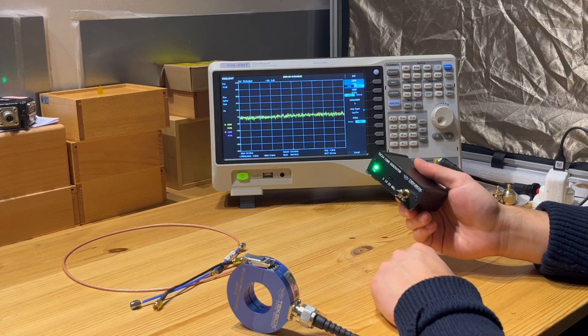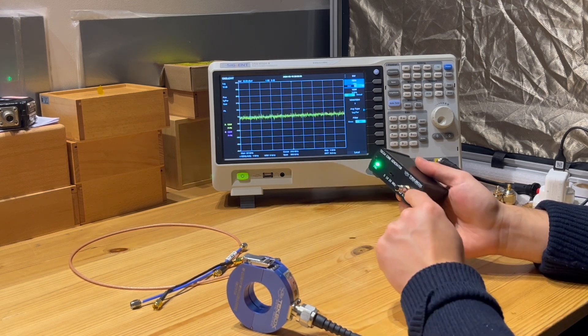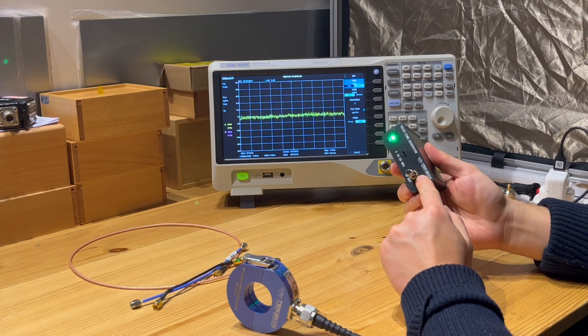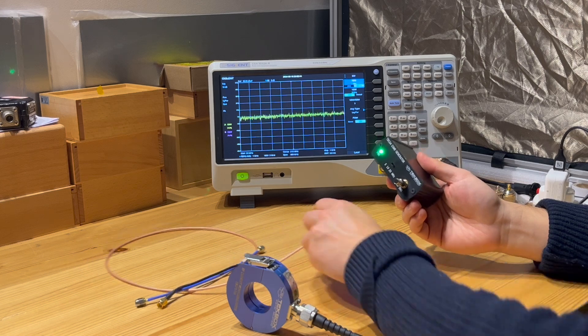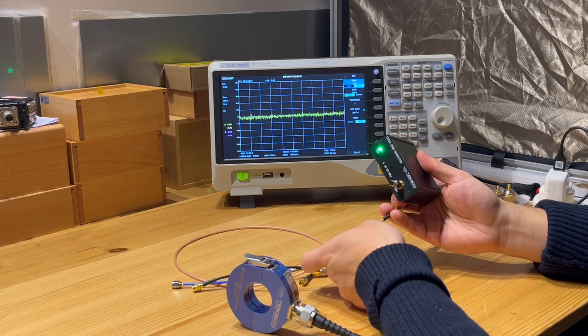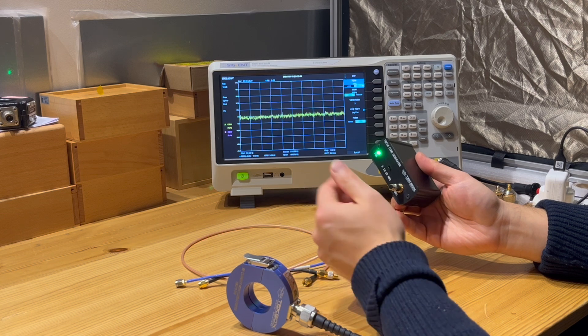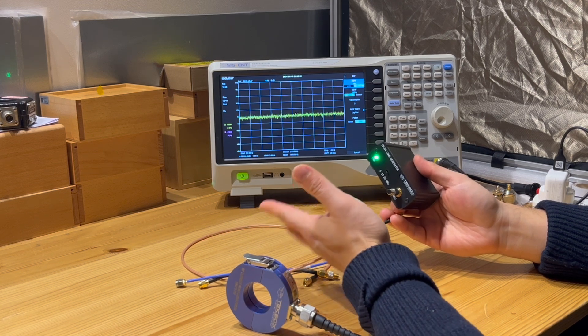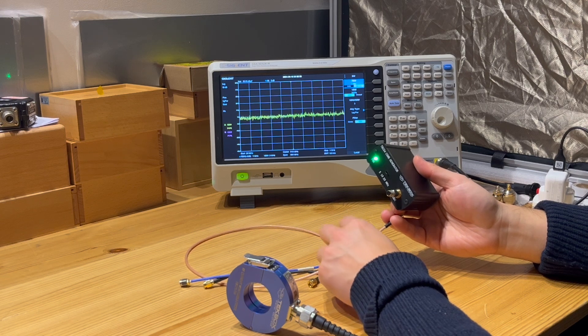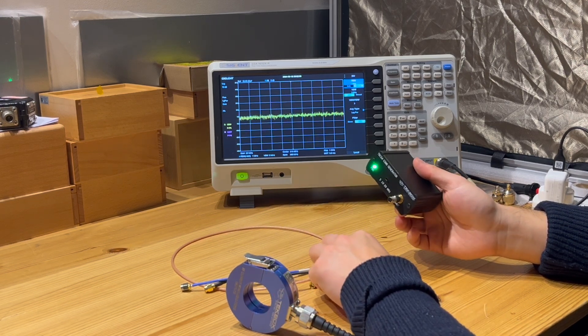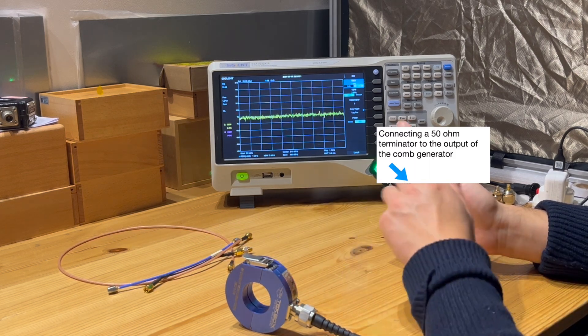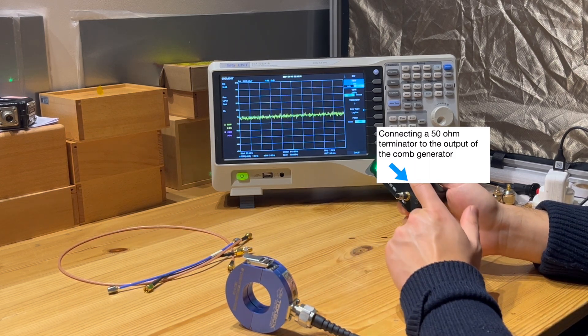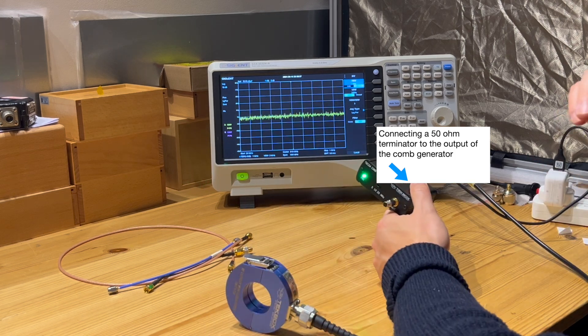So the first thing I need to do is to test whether the comb generator has a good shielding effectiveness itself. There's no point of using this to test shielded cable if there's leakage coming from the port. As we demonstrated in the past, if there's leakage leaking from this RF output, then you connect even with a very good quality shielded cable, you will have RF current on the outside of the shield.